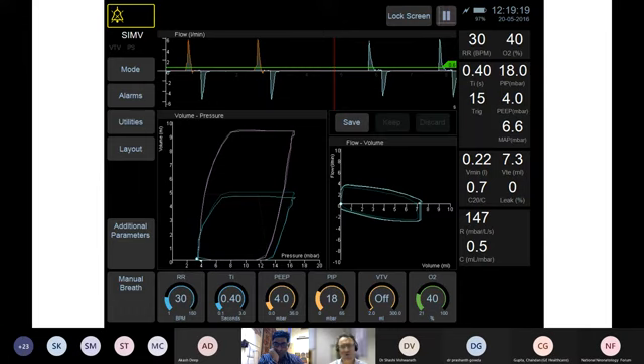So you see this little green line here. When the baby's effort breaks this line, then the ventilator will deliver a supporting breath. So we adjust the green line up and down depending on how much effort we want the baby to apply to their own ventilation, or depending how big the baby is and how large that breath is likely to be.